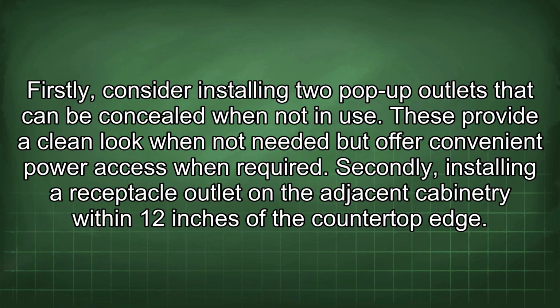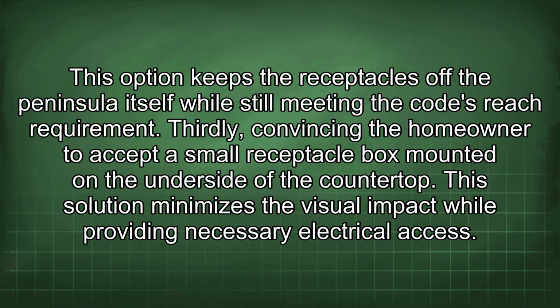Secondly, installing a receptacle outlet on the adjacent cabinetry within 12 inches of the countertop edge. This option keeps the receptacles off the peninsula itself while still meeting the code's reach requirement. Thirdly, convincing the homeowner to accept a small receptacle box mounted on the underside of the countertop. This solution minimizes the visual impact while providing necessary electrical access.